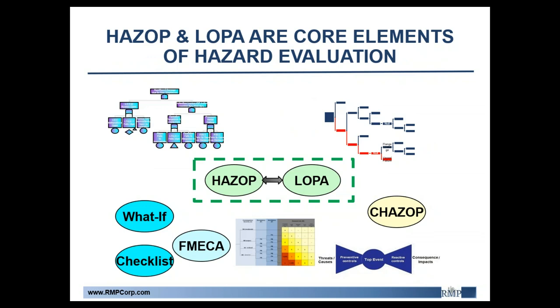There are several tools in the PHA toolkit for hazard analysis, such as what-if checklists, bow tie analysis, and so on. However, the team-oriented patterned brainstorming sessions associated with HAZOP studies are generally considered the workhorse of the industry. You can also fold in layer of protection analysis, or LOPA, into an integrated HAZOP study to provide additional insights, including identifying appropriate reliability targets for key safety features, providing a slightly quantitative approach. Although the core HAZOP approach hasn't really changed, HAZOP and LOPA applications have been evolving to accommodate higher expectations in quality and level of detail.